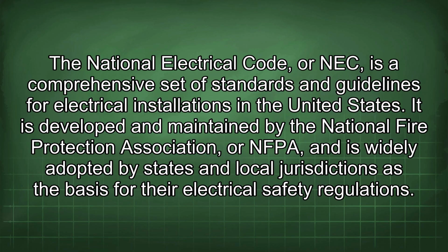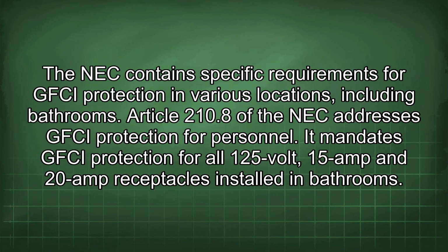The National Electrical Code, or NEC, is a comprehensive set of standards and guidelines for electrical installations in the United States. It is developed and maintained by the National Fire Protection Association, or NFPA, and is widely adopted by states and local jurisdictions as the basis for their electrical safety regulations. The NEC contains specific requirements for GFCI protection in various locations, including bathrooms. Article 210.8 of the NEC addresses GFCI protection for personnel. It mandates GFCI protection for all 125-volt, 15-amp and 20-amp receptacles installed in bathrooms.